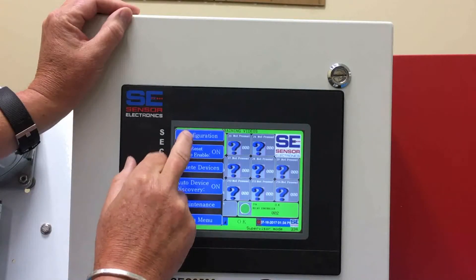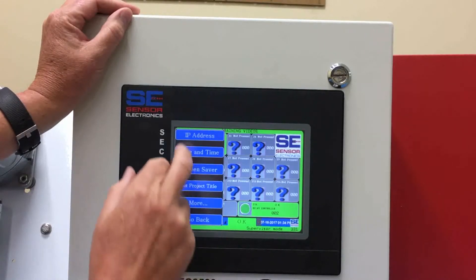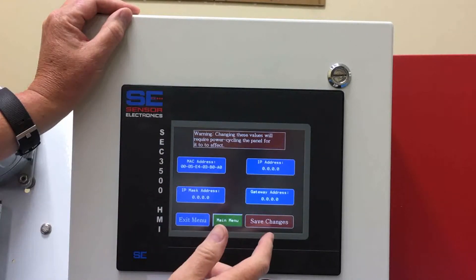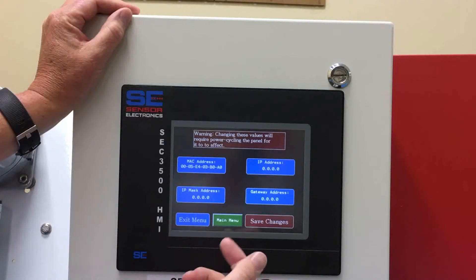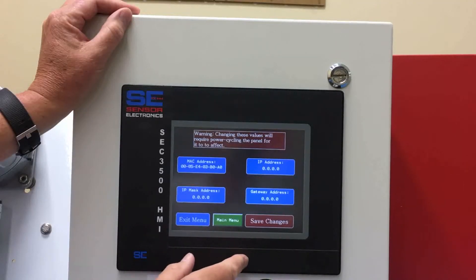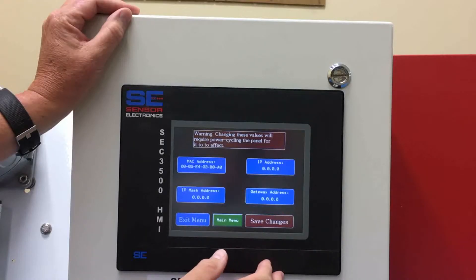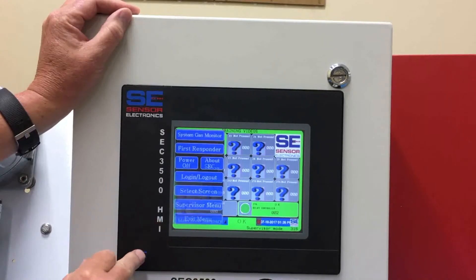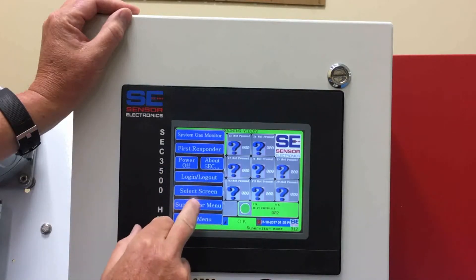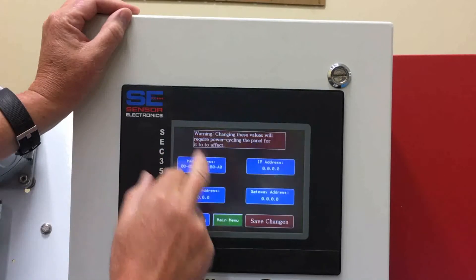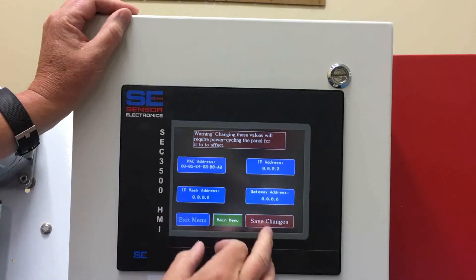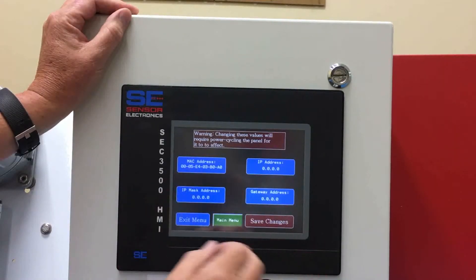If we go back up to configuration, through this menu structure you can add an IP address to the HMI panel. The HMI panel has an Ethernet port on the back side. You work with your IT person to program in the IP address and the gateway, then save those changes. After programming them in, you press the button, enter all the correct information, save changes, and that will reboot the panel.